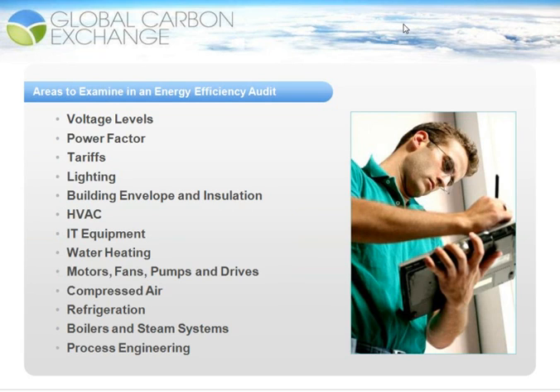A lot of people don't look at this as a start in an energy efficiency audit, but it's a crucial first step. Your voltage levels into a facility influence all energy-consuming devices, whether they be old inefficient devices or new electronic types of devices. Voltage levels can either be harmful, severely damaging, or simply increase your energy consumption. High and low voltage levels both lead to increased energy consumption as well as decreased equipment life, particularly in new efficient systems.